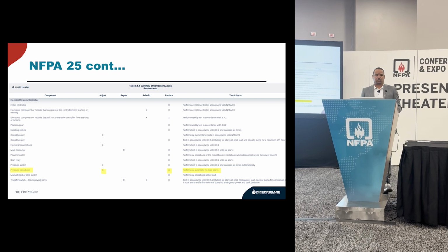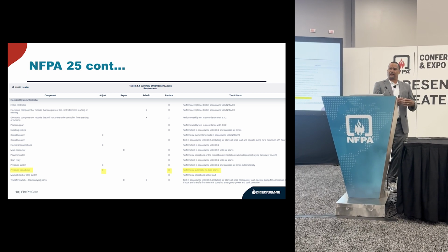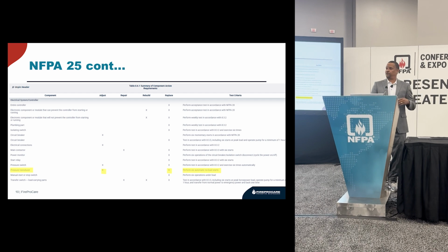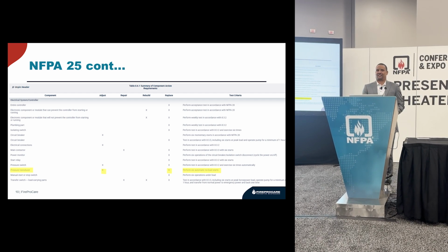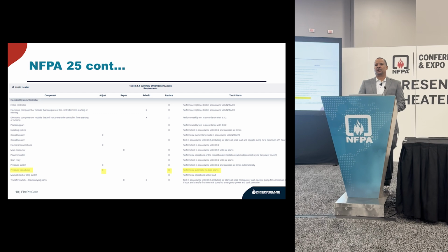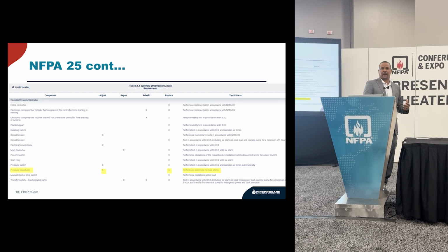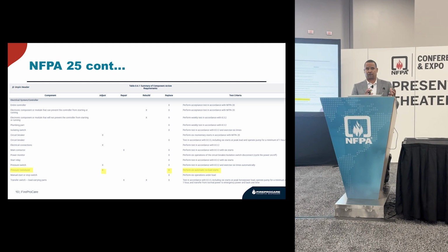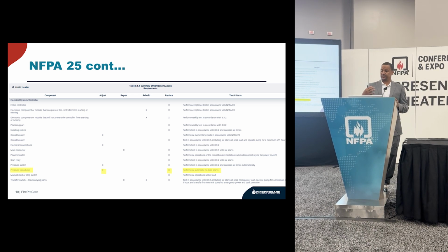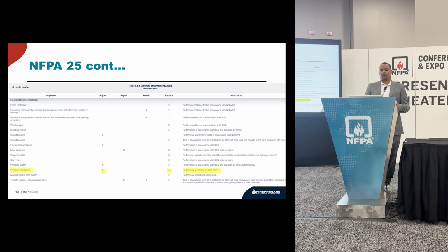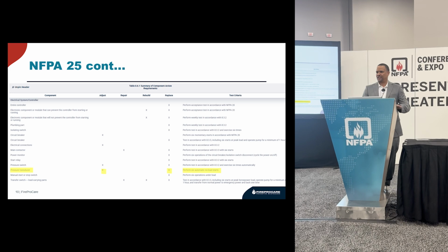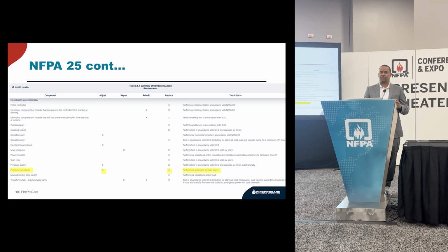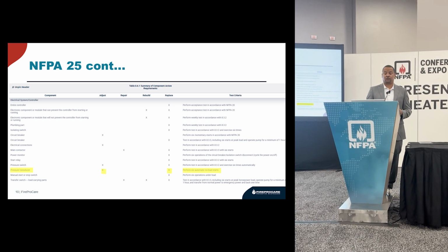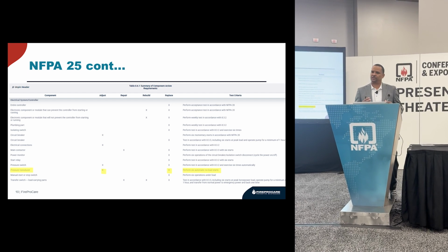I know electricians may go into the pump room, change out the transducer, turn it back on. If there's no alarm, they walk away. That's not correct. They should be utilizing NFPA 25, contacting the controller manufacturer, which is what they recommend. The committee was very specific about that. Always work with the controller manufacturer, because their information is the base. NFPA 25 is generic in nature. But if the controller manufacturer tells you you need to start it 20 times, you need to follow that.